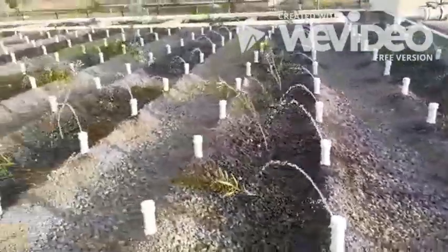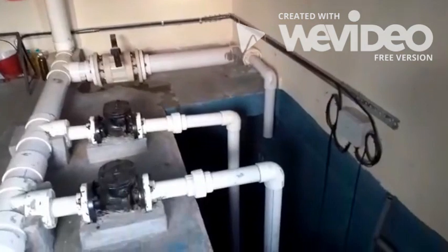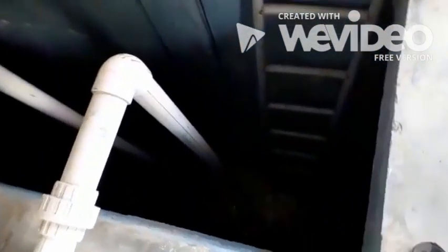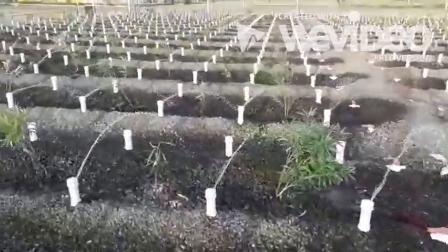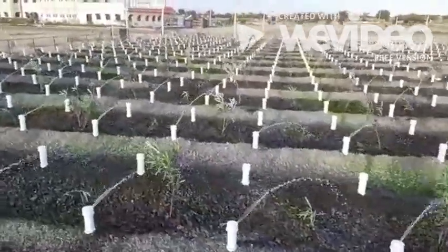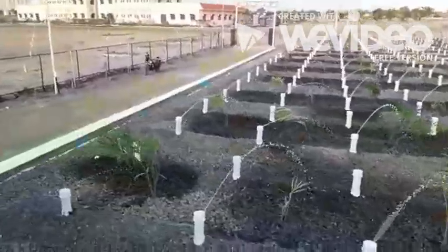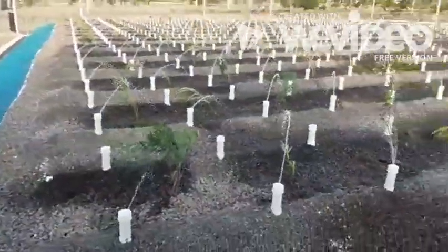In biomound 1, the water is evenly distributed and collected in collection tank 1. After collecting in collection tank 1, where the ammonia in the inlet water is converted to nitrate, this water is pumped along with the residual water into biomound 2, where final removal of the nitrogen by denitrification and residual COD takes place as it percolates through this reactor and is collected in collection tank 2.